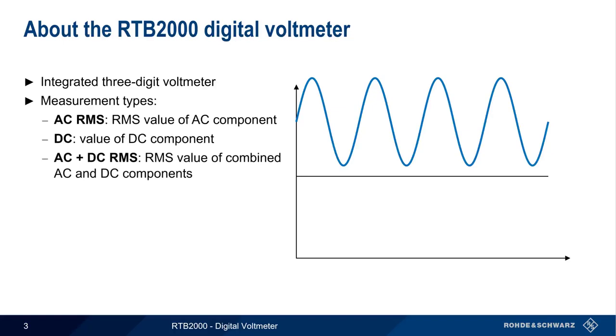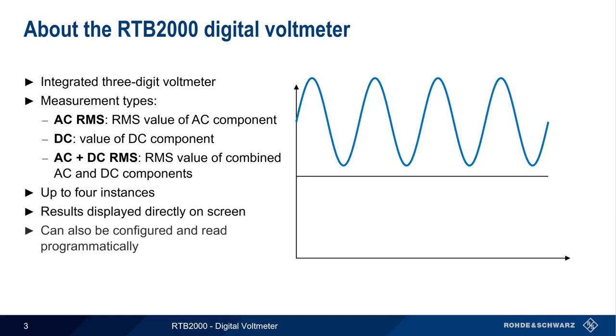The RTB supports up to four separate but simultaneous instances of the digital voltmeter. Results are displayed directly on the screen, but it's also possible to use programmatic control to configure and read values from the different meters. In the remainder of this presentation, we'll show step-by-step how to configure and use these digital voltmeters.